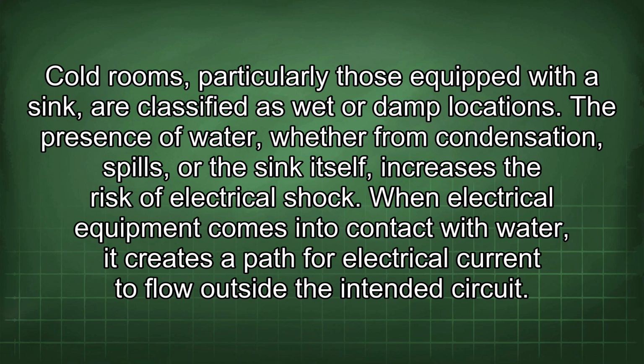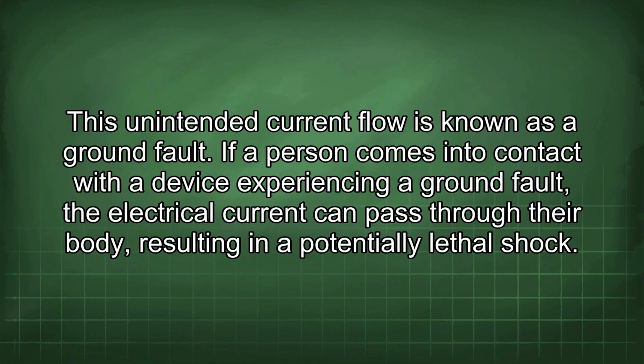Cold rooms, particularly those equipped with a sink, are classified as wet or damp locations. The presence of water, whether from condensation, spills, or the sink itself, increases the risk of electrical shock. When electrical equipment comes into contact with water, it creates a path for electrical current to flow outside the intended circuit. This unintended current flow is known as a ground fault. If a person comes into contact with a device experiencing a ground fault, the electrical current can pass through their body, resulting in a potentially lethal shock.